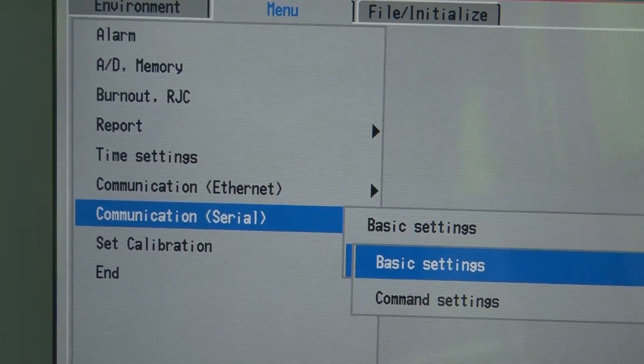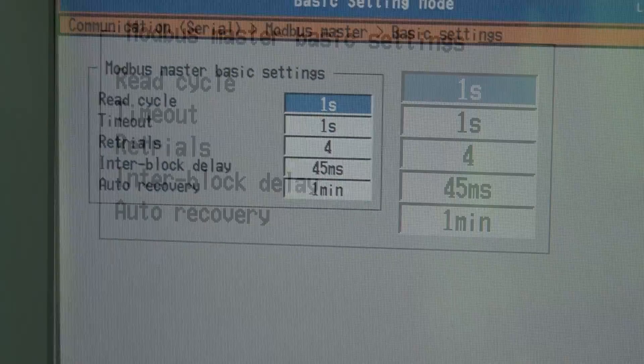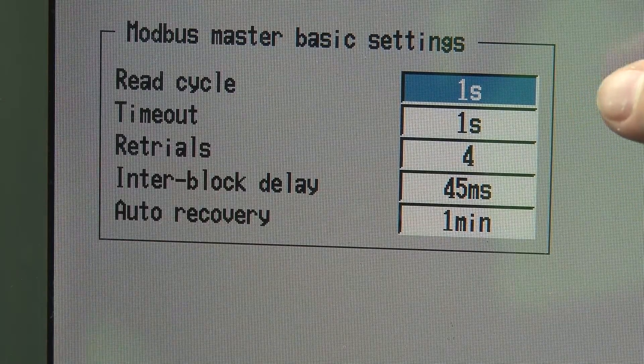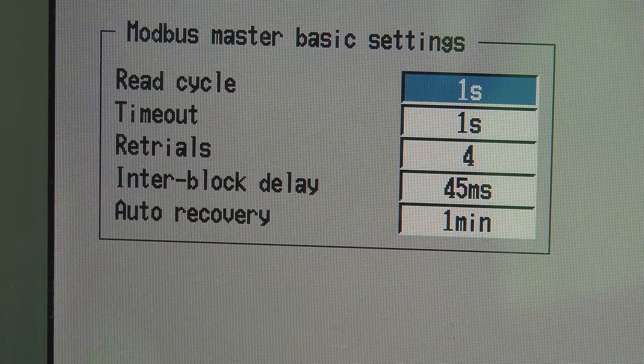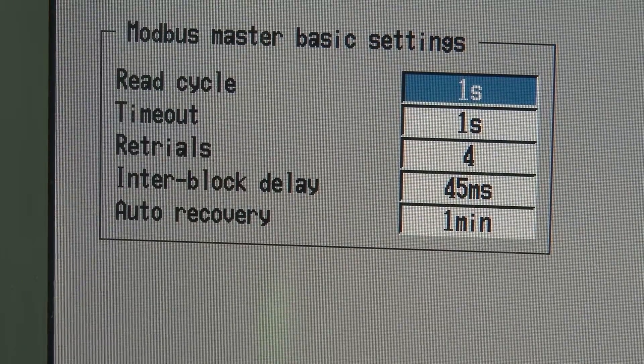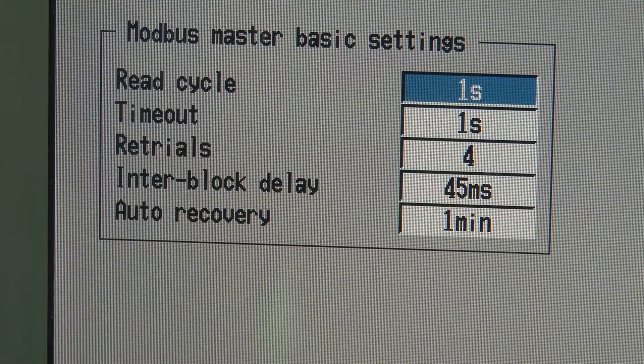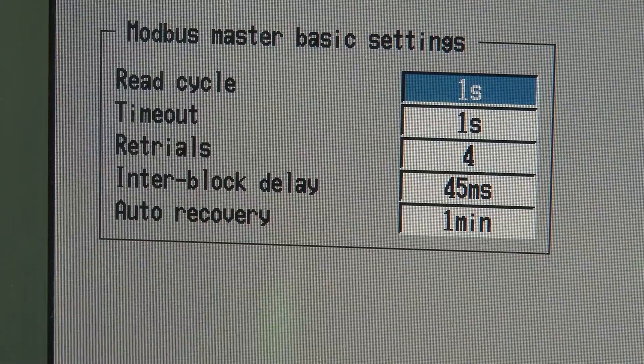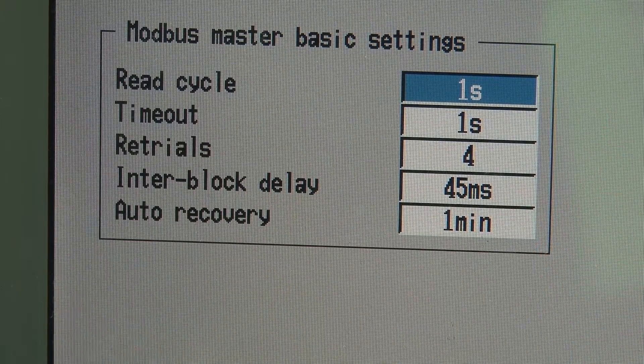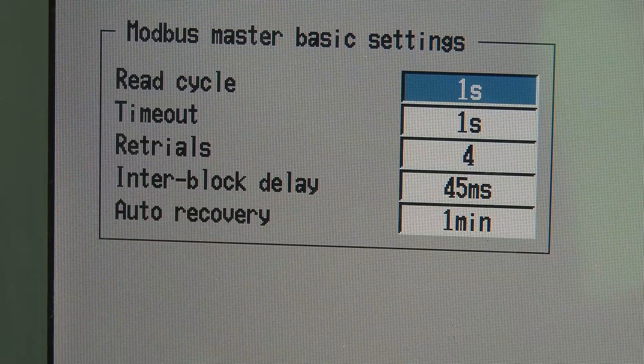Under the Modbus Master settings we find the basic setting menu. The read cycle is 1 second. The timeout is 1 second, meaning if the Modbus Master sends a command to the slave, it will wait 1 second for a response. If it doesn't get a response, it'll try again — in this case it's set for 4 retries — with an interblock delay of 45 milliseconds. If it fails after 4 retries, it will wait 1 minute and try again.